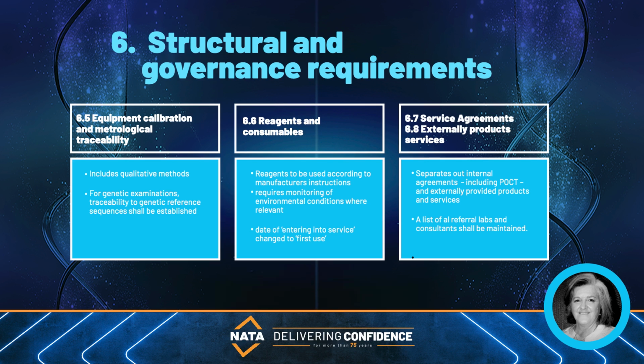Instructions for use shall be available for reagents, and they shall be used in accordance with manufacturer's instructions. Records for reagents shall be maintained, including the date of receipt and conditions when received, the expiry date, the date of first use, which was previously the date of entering into service, and, where applicable, the date the reagent or consumable was taken out of service. In-house reagents need to include reference to the preparer.